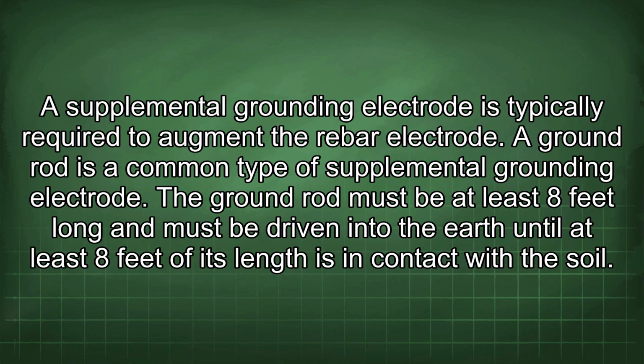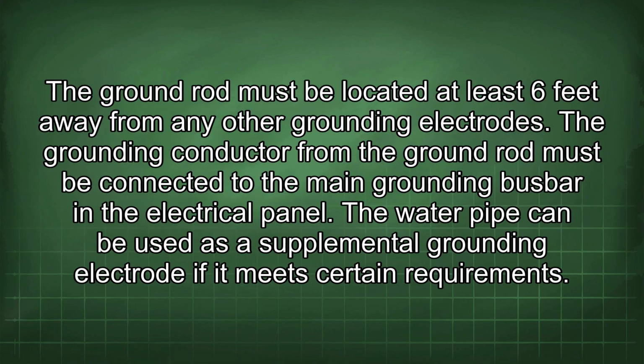A supplemental grounding electrode is typically required to augment the rebar electrode. A ground rod is a common type of supplemental grounding electrode. The ground rod must be at least 8 feet long and must be driven into the earth until at least 8 feet of its length is in contact with the soil. The ground rod must be located at least 6 feet away from any other grounding electrodes. The grounding conductor from the ground rod must be connected to the main grounding busbar in the electrical panel.